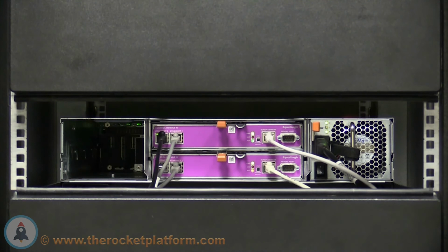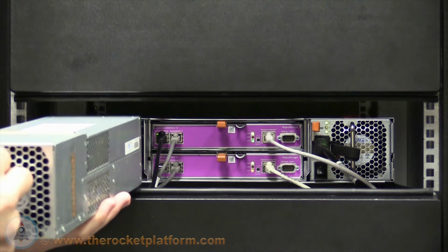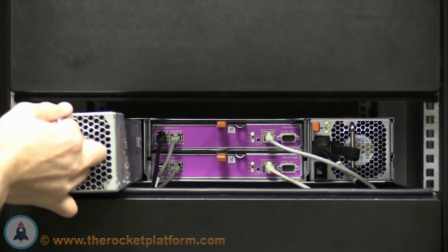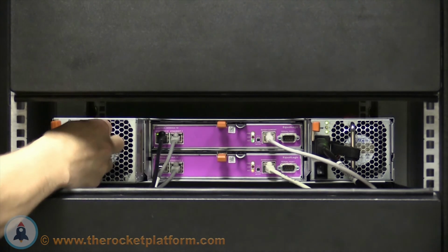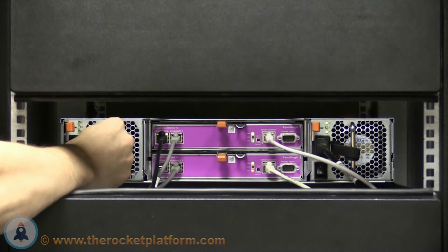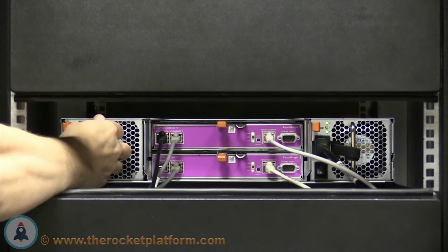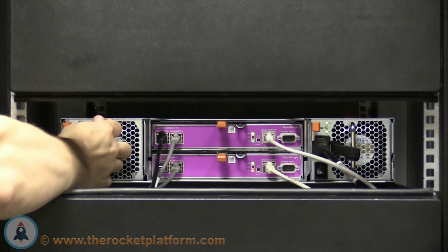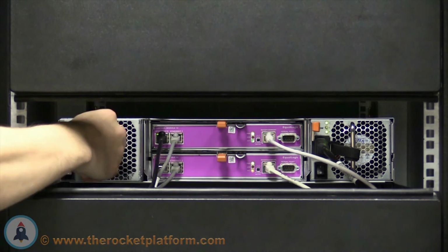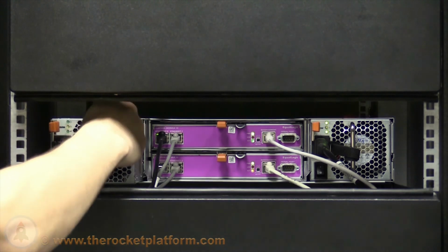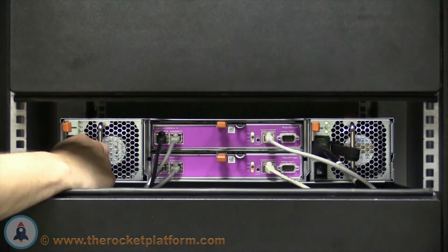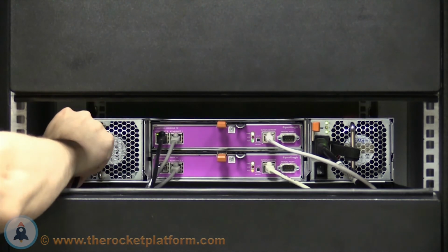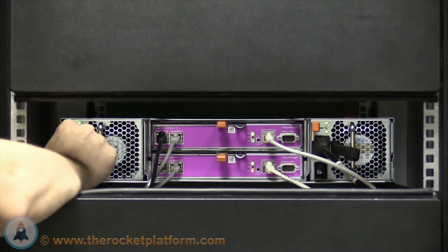Insert the new power supply until you hear or see the orange tab click into place. Pull back on the metal bar without releasing the locking mechanism to ensure that the power supply has been seated properly. If the supply stays in its slot, it has been properly seated. If the supply moves around in the slot, reseat the power supply until properly seated. Plug the cable into the power supply and ensure the switch on this power supply is in the on position.